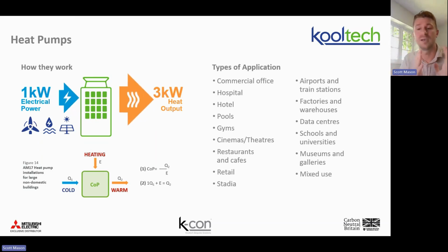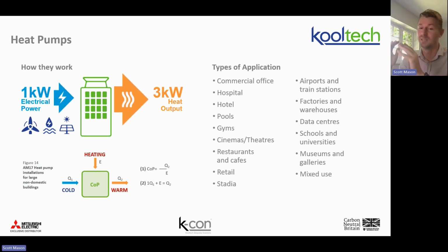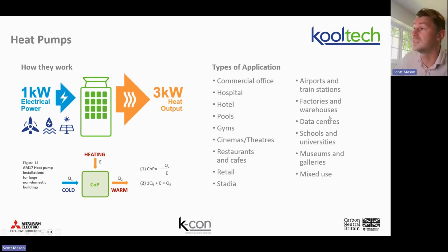As a result, the air source heat pump can be this size, which means over the course of the year, we're looking at a contribution of 75% from the air source heat pump technology, because actually that peak load, the final 10% of operation, is probably about 30–40% of your actual heat load for the building, because it just is those days where you need the heat and you need that top up. So then we look at bivalent applications and things like this. But even on a bivalent system, you can get very solid carbon savings. So it depends what the drivers are for the job.